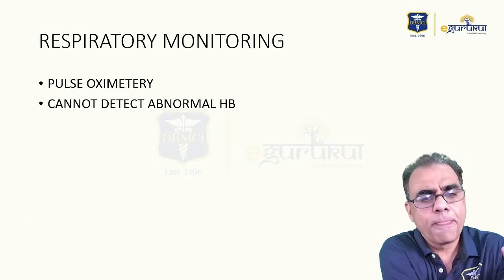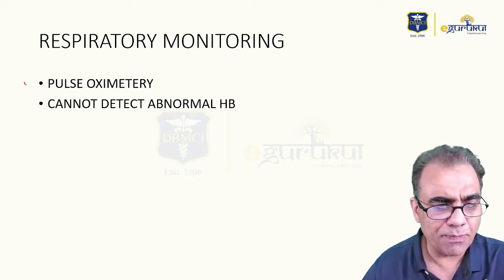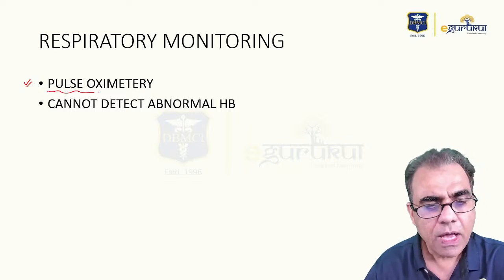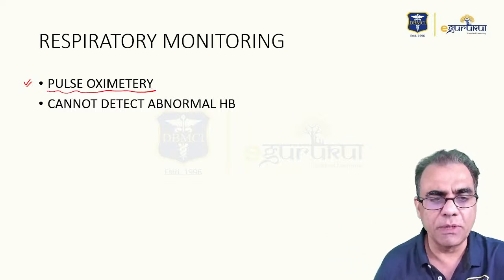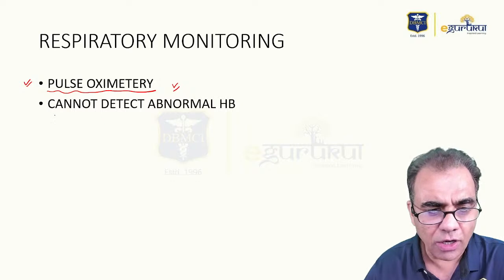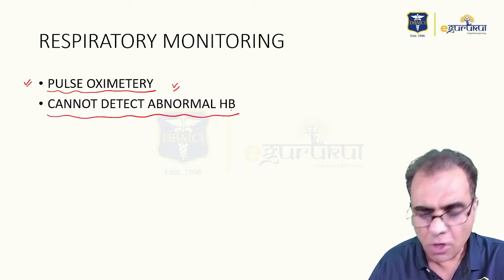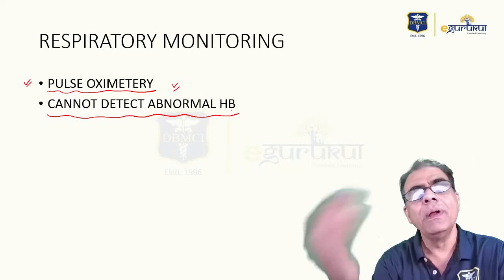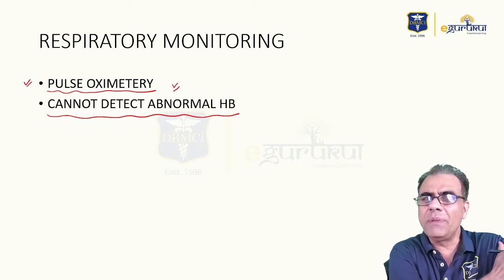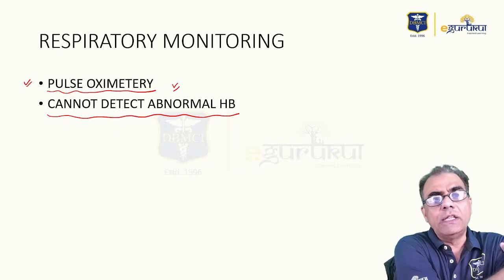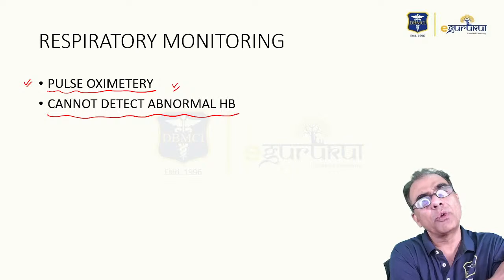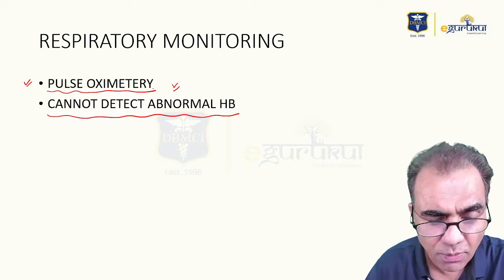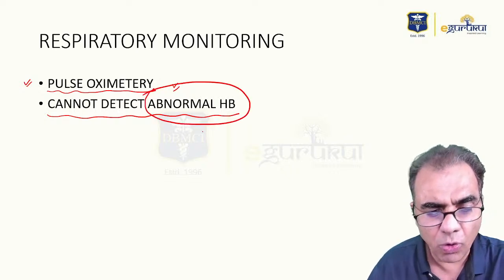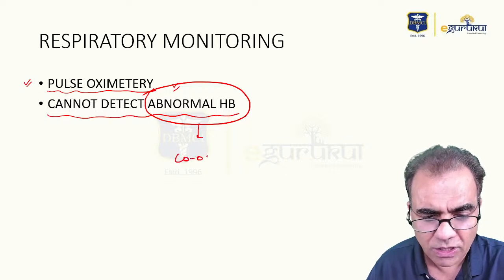Respiratory monitoring: the most basic is pulse oximetry. But the disadvantage of pulse oximetry is that it cannot detect abnormal hemoglobin. So if the patient is suffering from any kind of methemoglobinemia or sulfhemoglobinemia, the pulse oximeter will not be able to detect it. These abnormal hemoglobins can be detected only by co-oximeters.